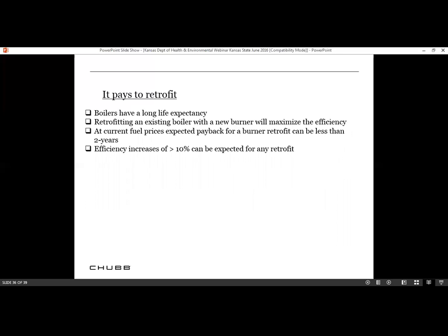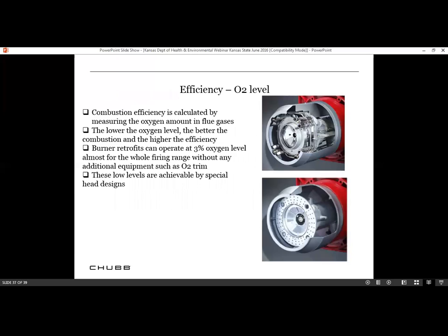It pays to retrofit. Boilers have a long life expectancy. Retrofitting an existing boiler with a new burner will maximize the efficiency. And normally you get a payback of about 2 years, and the efficiency increase is greater than 10% when you do a retrofit of a large boiler with a new burner. And the reason for that is the O2 level, and if you look at the photo on the right, it's the burner heads. The designs are totally different than what we've seen in the past, and they're able to get the O2 trim within criteria, and we're able to operate at 3% oxygen levels.